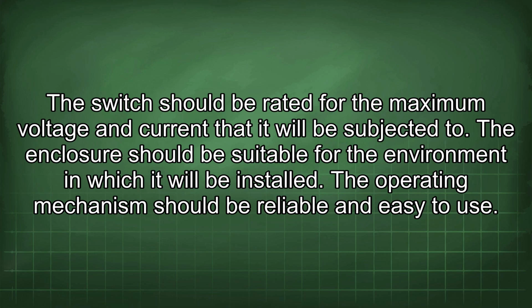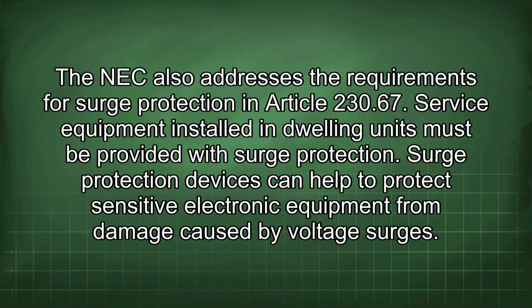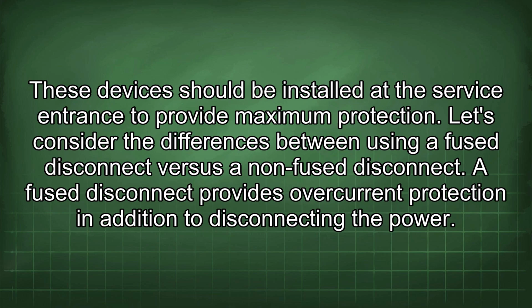The enclosure should be suitable for the environment in which it will be installed. The operating mechanism should be reliable and easy to use. The NEC also addresses the requirements for surge protection in Article 230.67. Service equipment installed in dwelling units must be provided with surge protection. Surge protection devices can help to protect sensitive electronic equipment from damage caused by voltage surges. These devices should be installed at the service entrance to provide maximum protection.